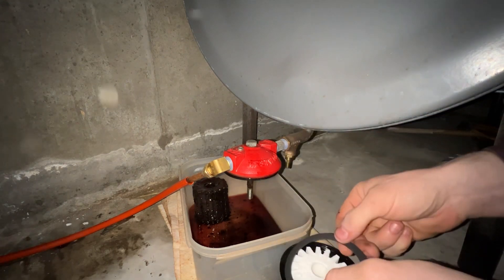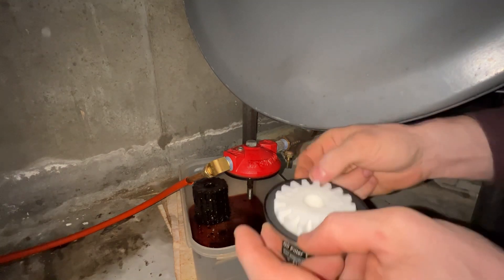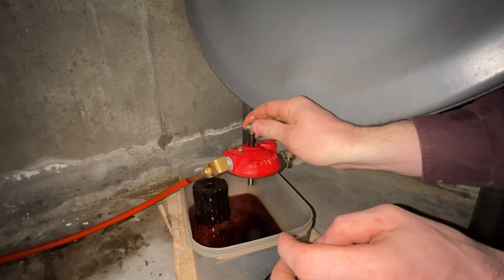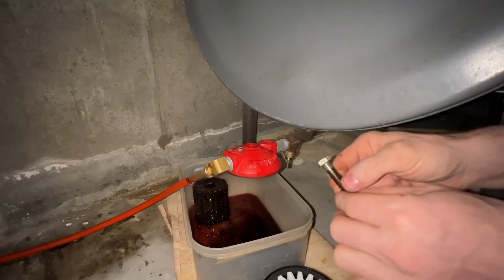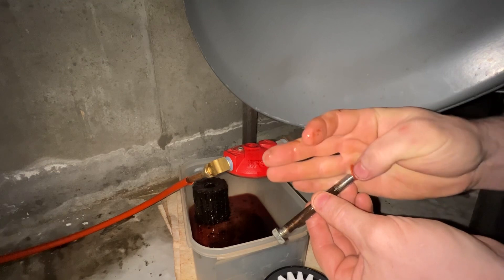Put the new gasket on the cup just like so — make sure you pull the old one off first. Then remove the bolt because there is also one more gasket that goes between the head and the bolt, so take the new one and put that on there as well.